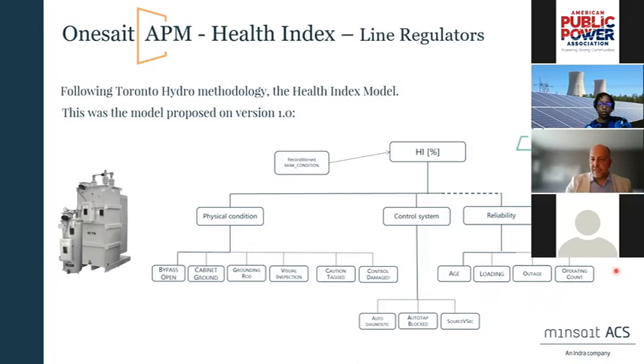This information comes from different data sources. Age comes from your asset management system, loading may come from your SCADA, outages may come from the outage management system or SCADA as well, and so does the operating count—unless there's a specific system connected to the line regulator that counts operations, or the line regulator requires a physical inspection to provide that information.